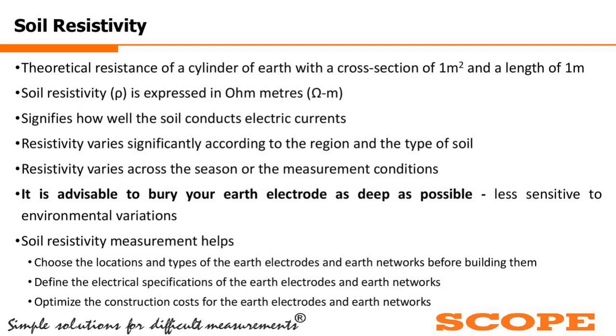So soil resistance, or the earth pit resistance, is measured in ohms, the basic resistance unit. But resistivity is expressed in ohm meters. It signifies how well the soil conducts electrical current. Resistivity varies significantly according to the region and the type of soil. If the type of soil changes from rocky to muddy, the resistivity of that soil will change. Resistivity also varies across the seasons and the measurement conditions. How I am measuring is going to give me different resistivity values.